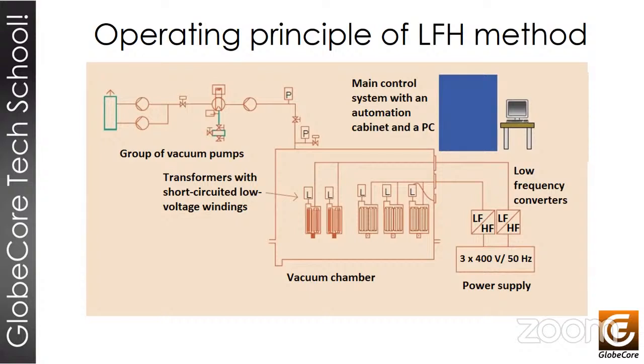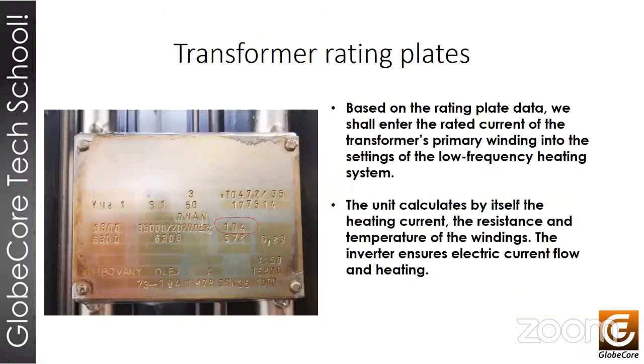Monitoring the vacuum level is necessary because the breakdown voltage is reduced in vacuum, and continuous monitoring of the temperatures of the high voltage and low voltage windings allows optimizing the drying process. So let's figure out what we need to operate a transformer. Each transformer has a data plate. We will need to find the parameters required.